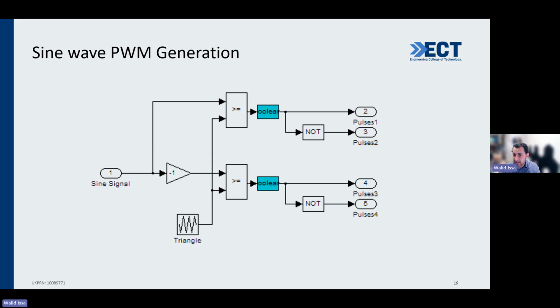About the technicality again, we have inverters and switches. This shows an example of how the inverters generate a sine wave. They use a sine wave as reference and generate something called PWM for the switches. This PWM is a high frequency pulsation, on and off, but it modulates a sine wave. After passing that signal through a low pass filter, the LCL filter shown in previous slides, a pure sine wave comes out. This technique minimizes the size of the filter and the inverter, and makes the control more robust, because we can generate any sine wave, with any frequency and amplitude, very fast.